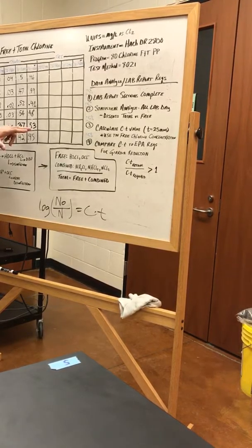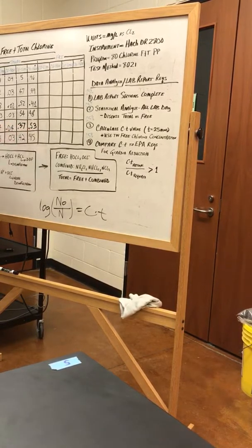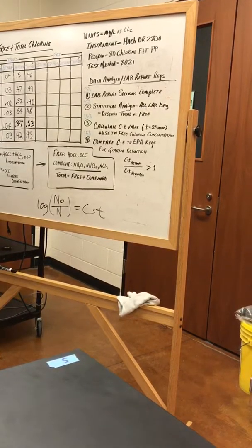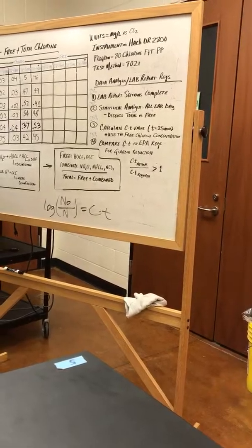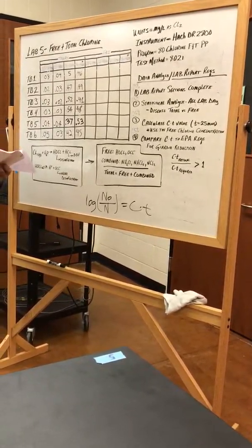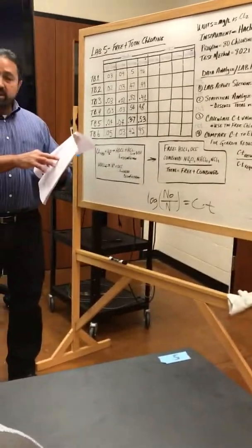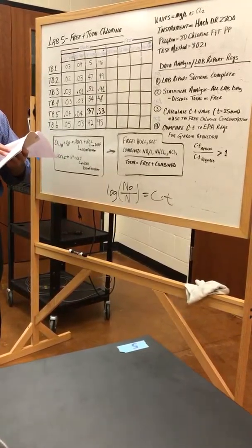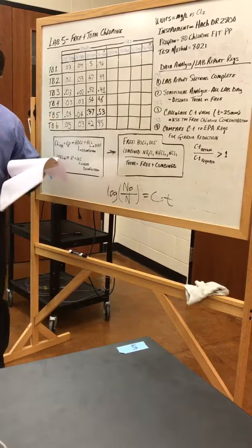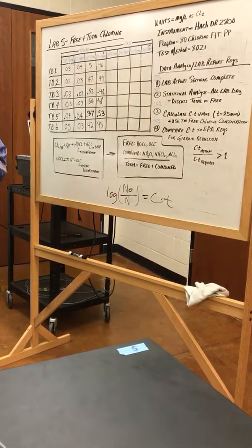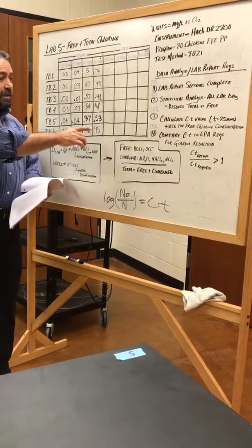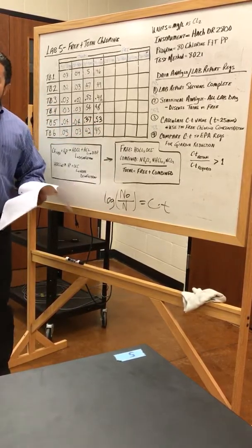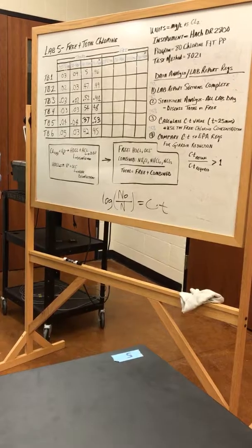We're going to assume 25 minutes, because if you look in your handout, this last part talks about contact time, 25 minutes in a pipe. Since we're comparing the given information to your actual information, we're going to use the same time so we can compare apples to apples. So you multiply your concentration times 25 minutes, and that would be your actual CT value.